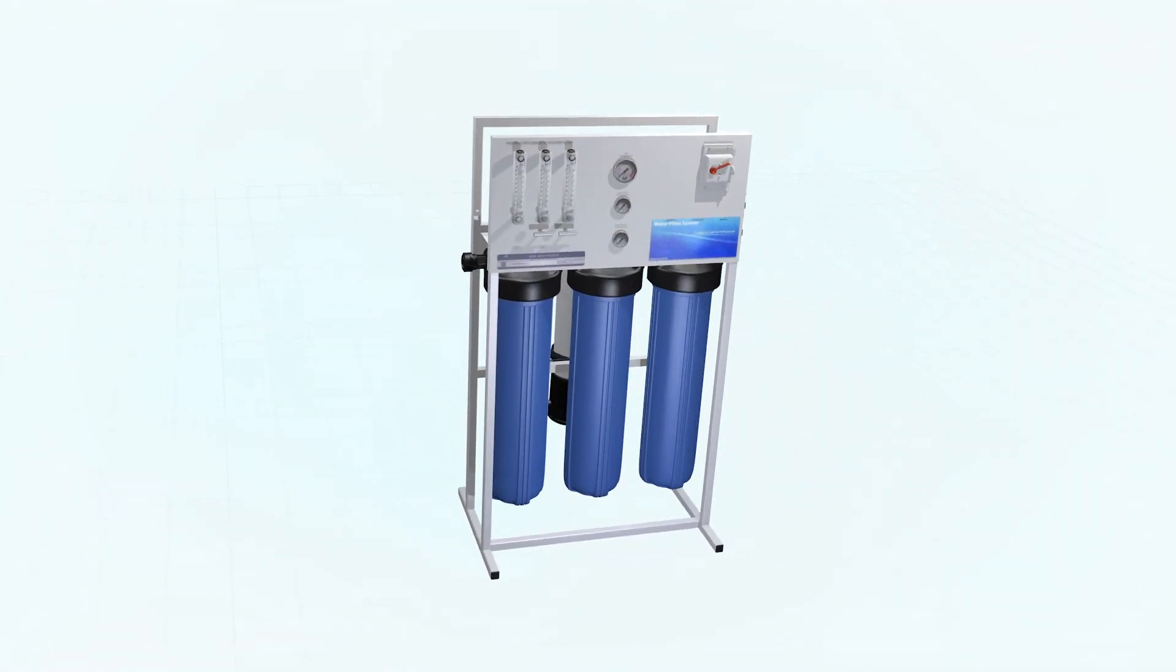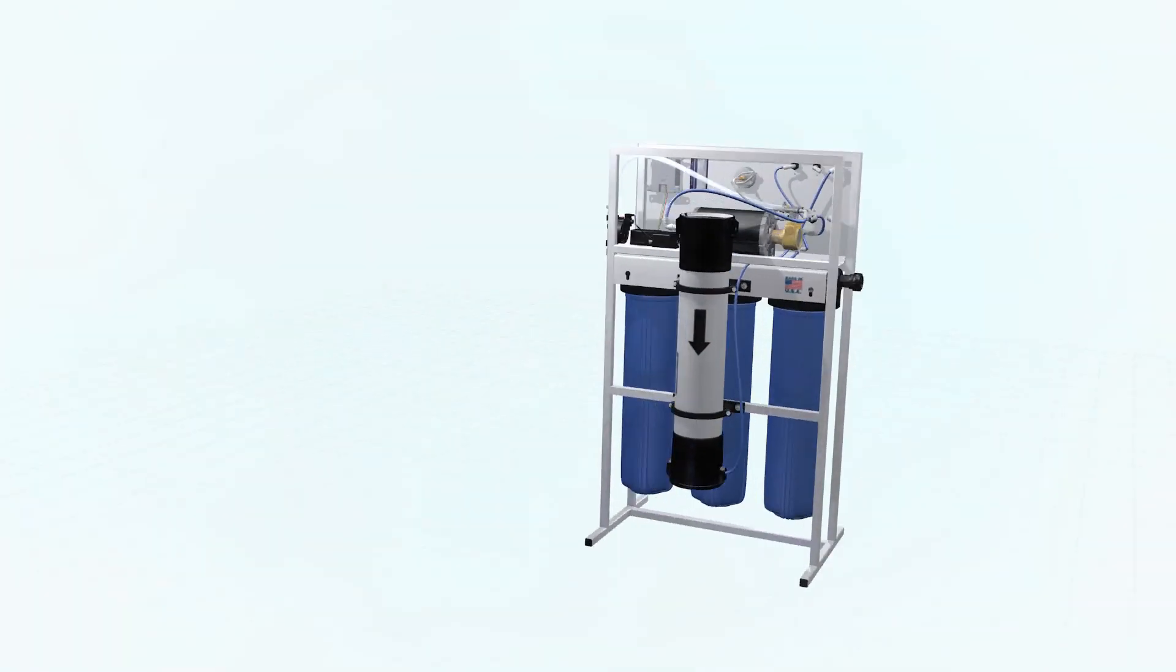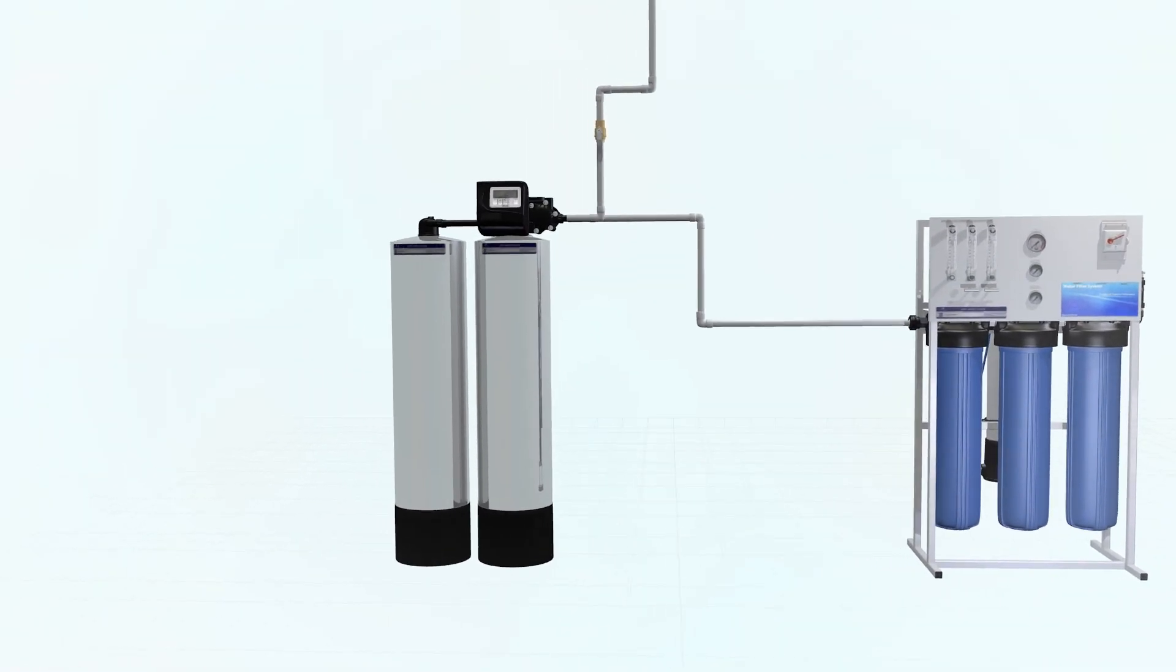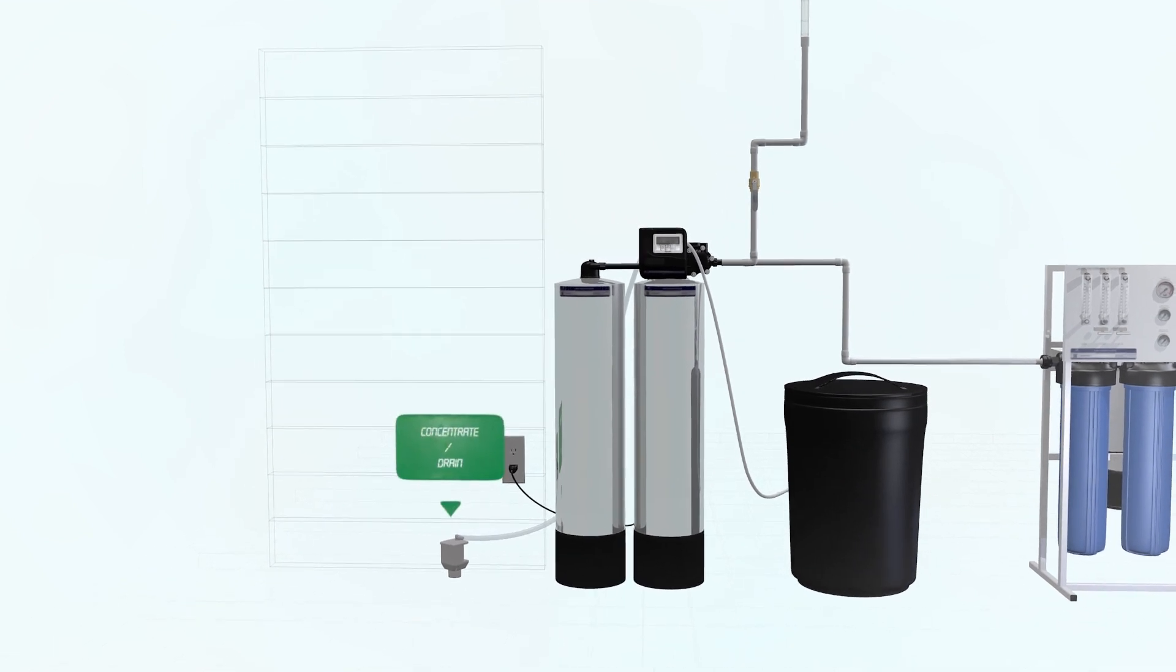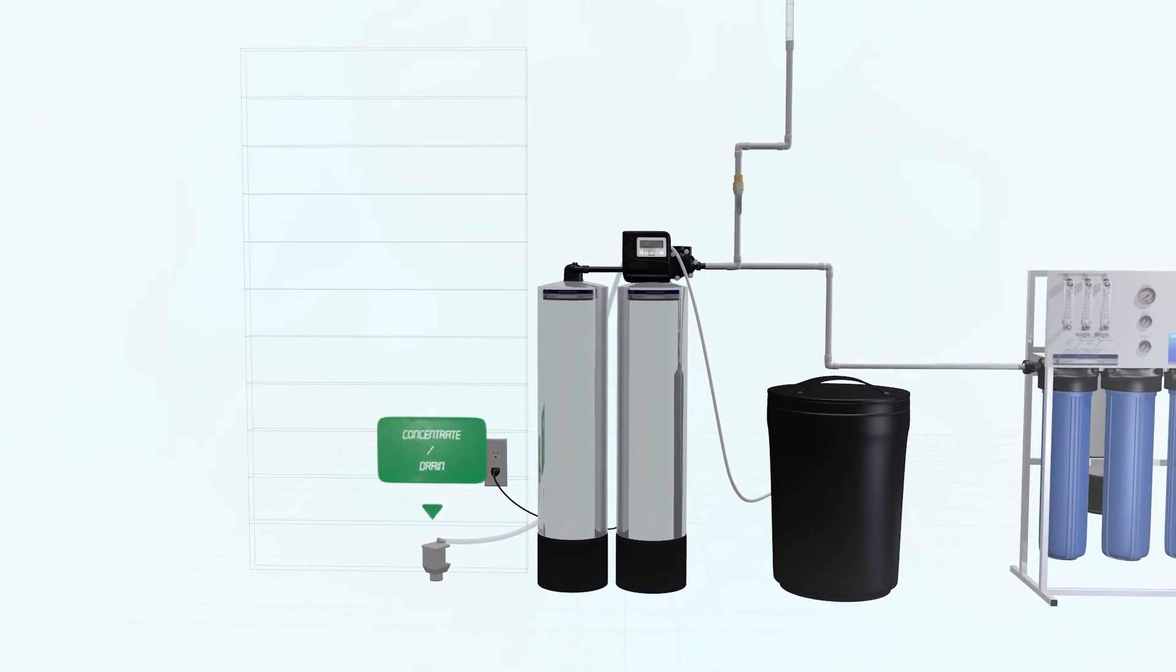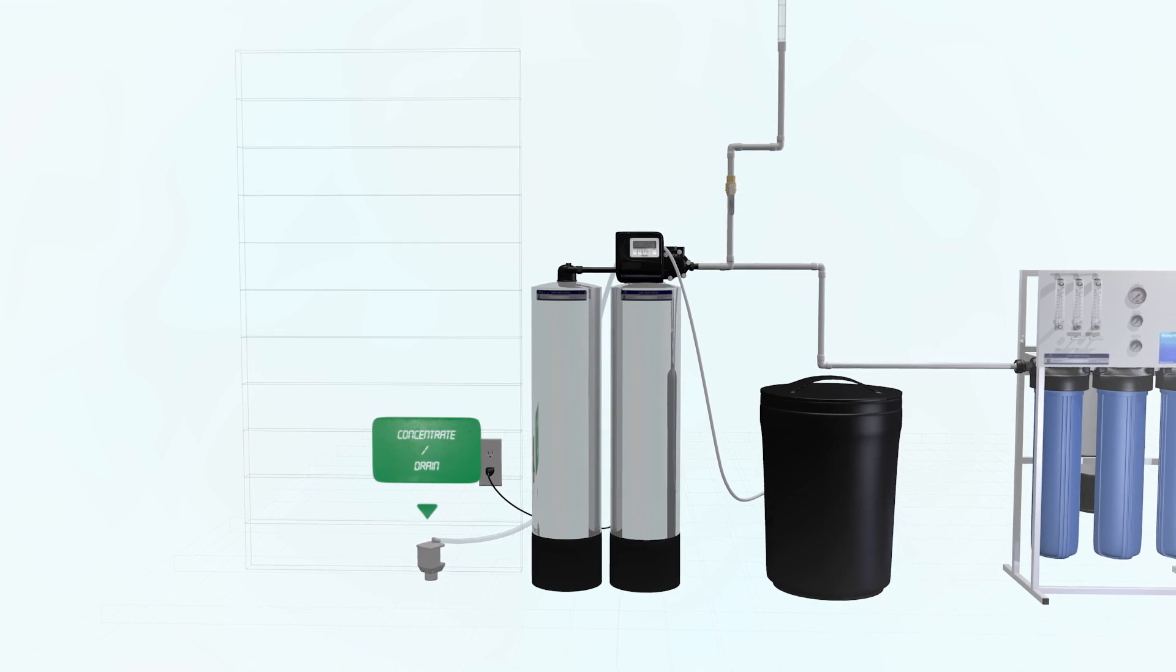APEX strongly recommends using a twin alternating water softener to soften the feed water and remove iron to protect the RO membrane. Hard water and iron can precipitate and damage the reverse osmosis membrane.